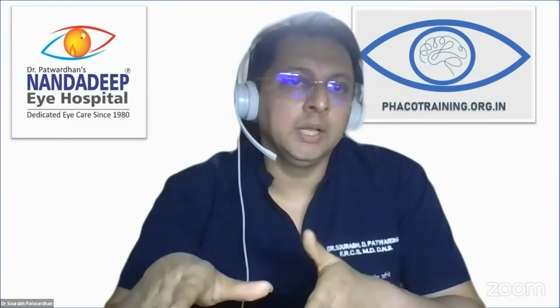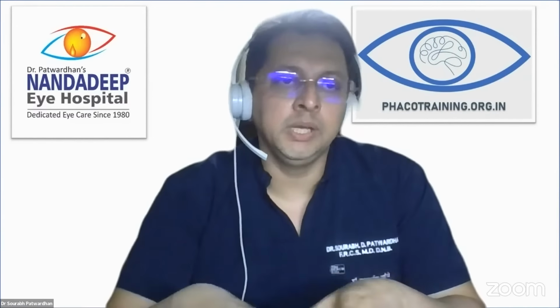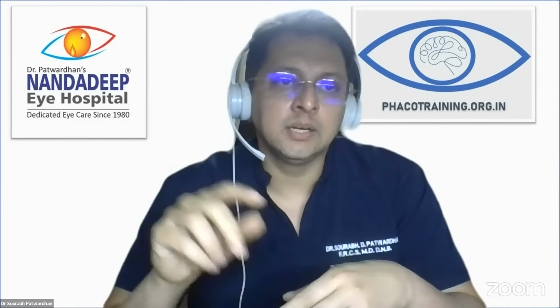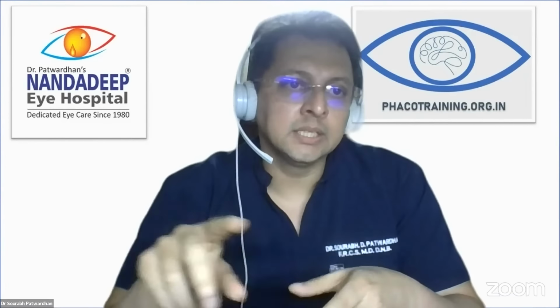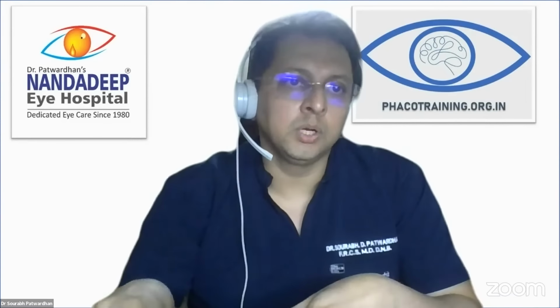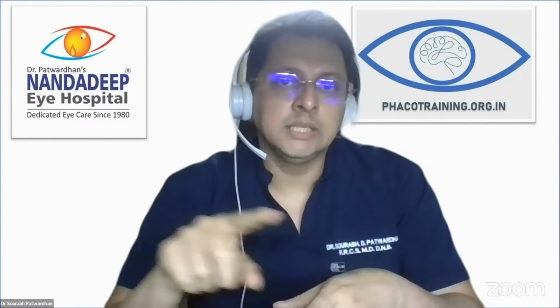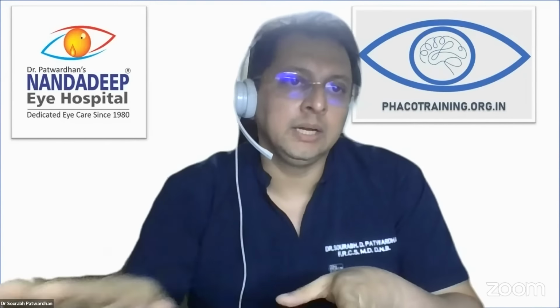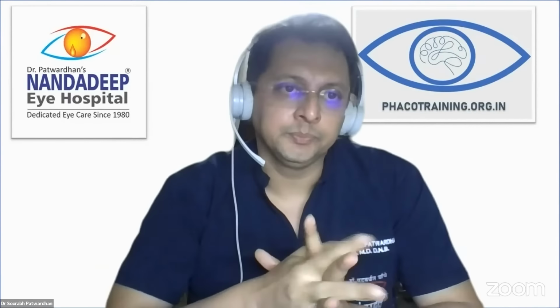Even for phaco probes, what I do once I walk in for my phaco surgery, the first thing I ask my assistant to show me is two things. One is the class 5 indicator of the phaco probe or IA probe. And second thing is the helix test, whether it was put in that or not. So once it has passed the helix test and it has passed the class 5 indicator, I am sure that the sterilization is complete. You do helix test for every set.